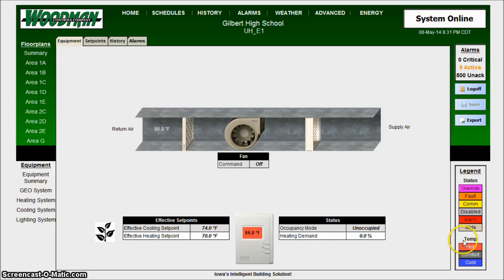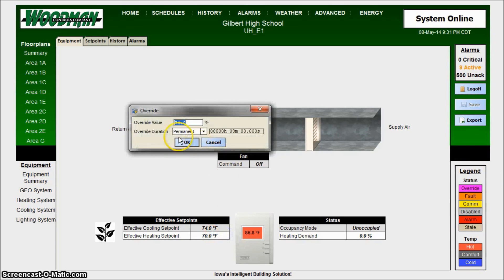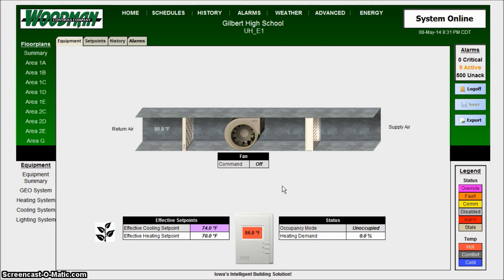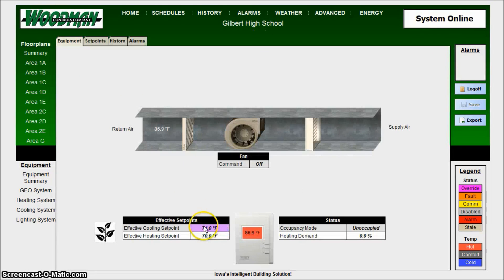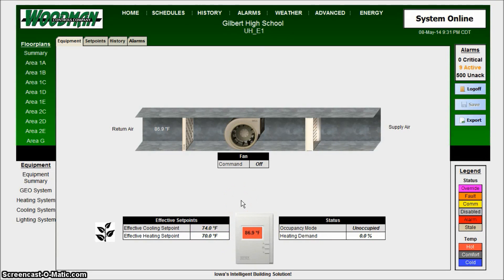The legend at the bottom appears on every screen, no matter what you're working on. There are background colors indicating status: override will show an override color, something broken turns orange, and yellow means offline. For example, this room is warm, so the space temperature is showing red — and you can see the same red temperature indicator back on the floor plan so you know it's warm. This has been a brief overview of the navigation system for Woodman Controls. If you have any questions, feel free to give us a call — thank you.